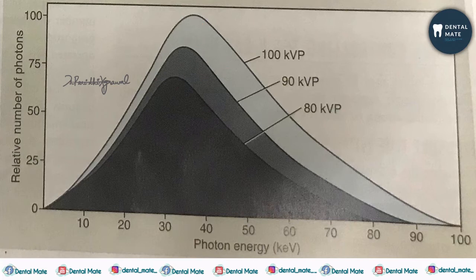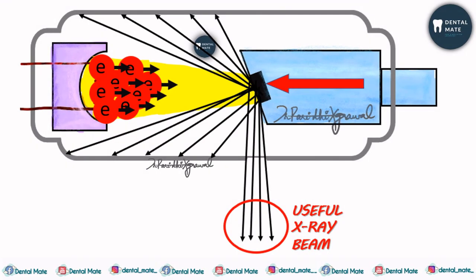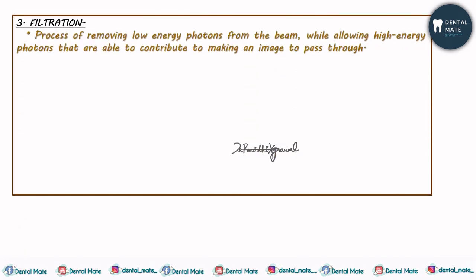Of the continuous spectrum of x-ray photons, only photons with sufficient energy penetrate through the anatomic structures and reach the image receptors, which could be either a digital image receptor or the x-ray film. The lower-energy photons that do not reach the receptors contribute to patient risk. Therefore, it is better to remove these lower-energy photons through a process called filtration — removing lower-energy photons from the beam while allowing high-energy photons that contribute to image formation to pass through.